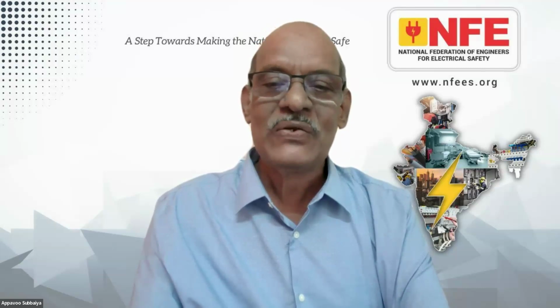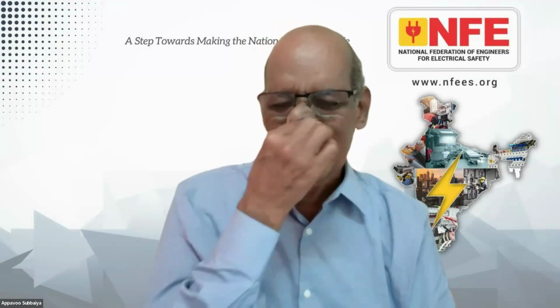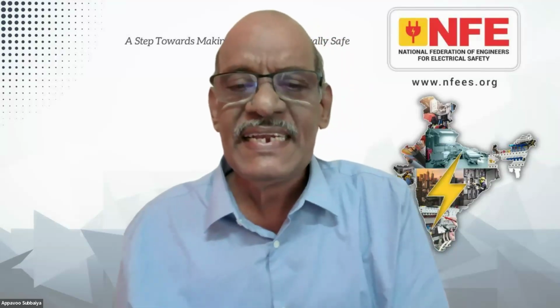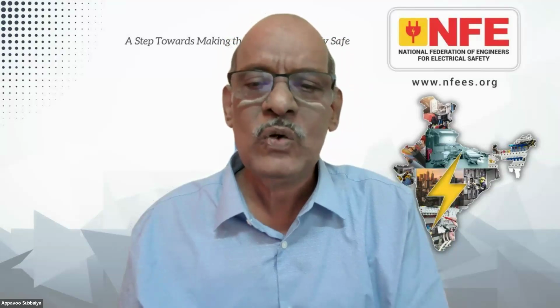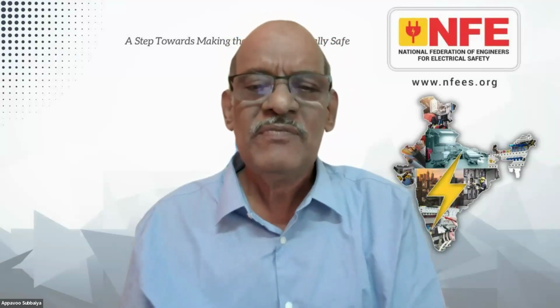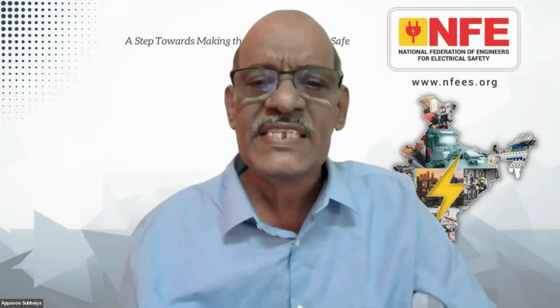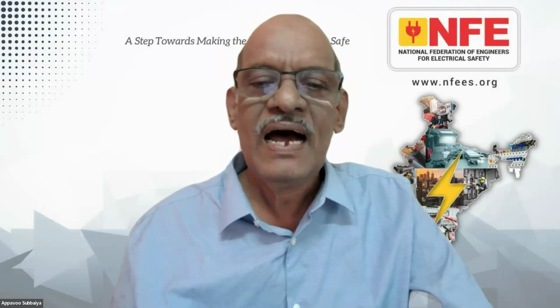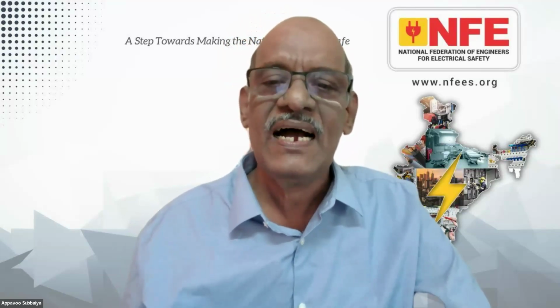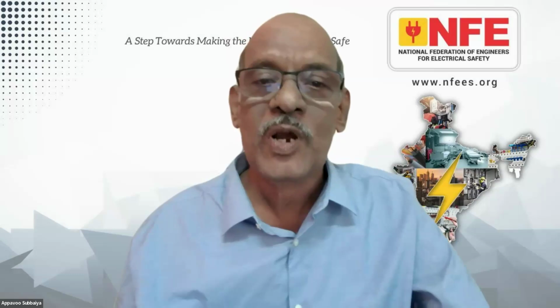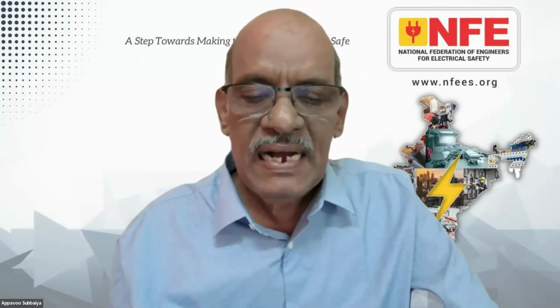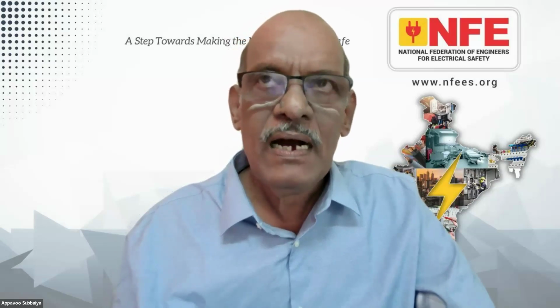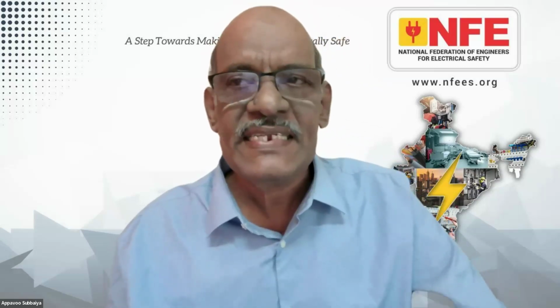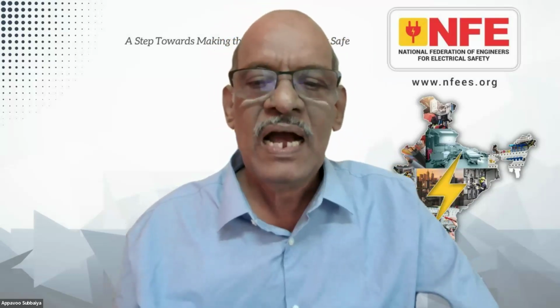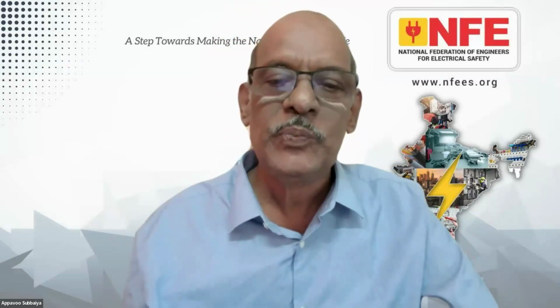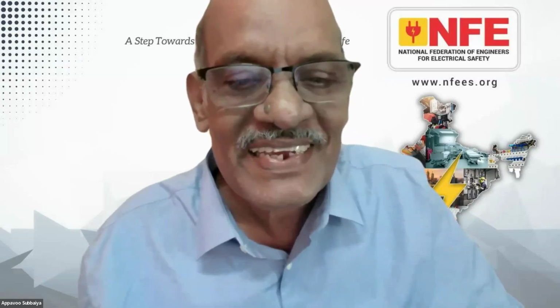It is not the number of earth electrodes or earth connections that you are giving. It is simply the interconnection at a common point, with no further downstream earthing. So what people are doing, providing so many earth electrodes, is a misconception. There will be a circulating current and many things which can affect people and property. So we have to adopt IS 732 and have an integration, a synergy, with the supplier's network: assess the supplier's network and provide our own network to protect our equipment and personnel.